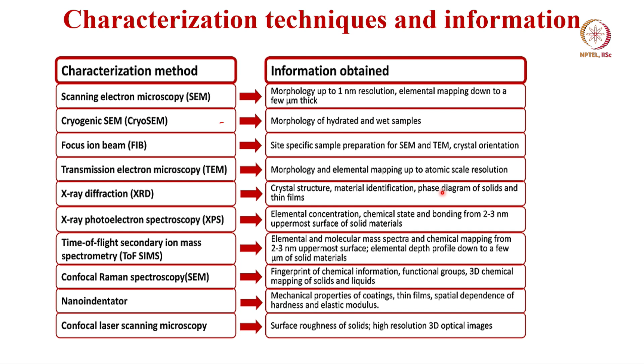Now, scanning electron microscope, as the name suggests, uses an electron beam, and this is an accelerated electron beam, typically accelerated around 20-25 kilovolt. So, this is a stage, and here your samples are kept. This is the door through which you can push the samples inside the microscope chamber. This chamber is kept under tight vacuum, right, and this is your electron beam line. This electron gun is here, and you have either a tungsten filament or a lanthanum hexaboride filament, LaB6, and you have a gun alignment control and a pneumatic airlock valve.